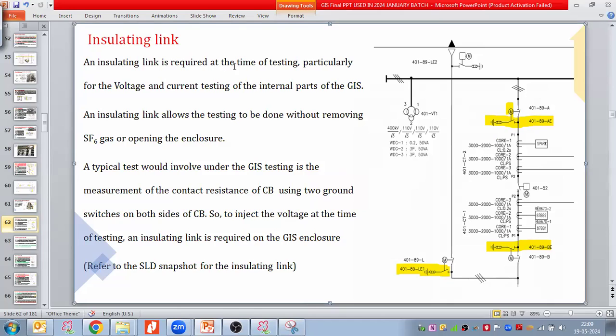So an insulating link is required at the time of testing, particularly for the voltage and current injection testing of the internal part of the GIS. An insulating link allows the testing to be done without removing gas or opening the enclosure. So through this insulating link, we can do direct internal tests. A typical test under the GIS testing is the measurement of the contact resistance of the breaker, that is, how much the resistance is across the breaker. So for that, we need to do the test using two ground switches on both sides of the circuit breaker. So close both side ground switches, and then we do the contact resistance testing of the breaker. So this test is achieved by this insulating link.